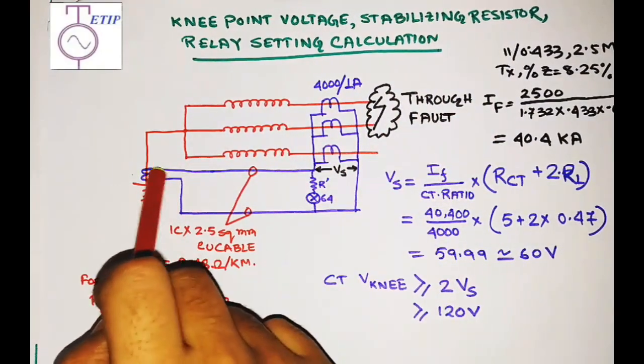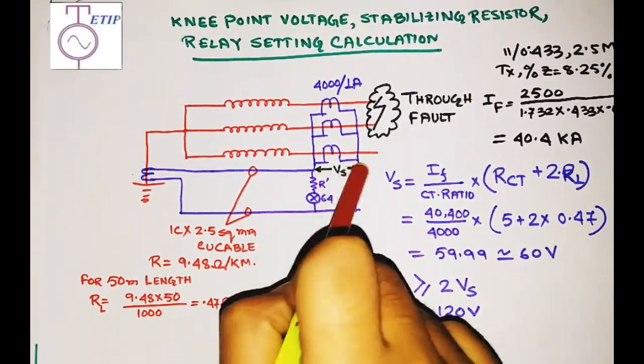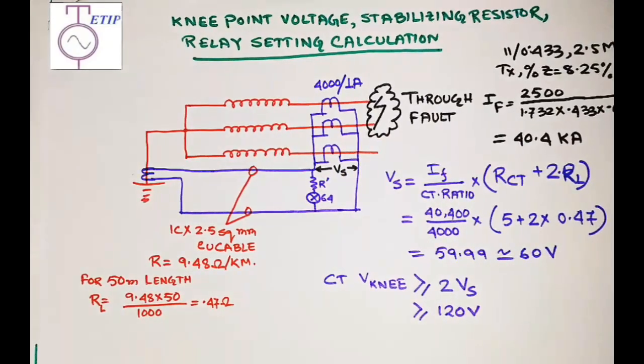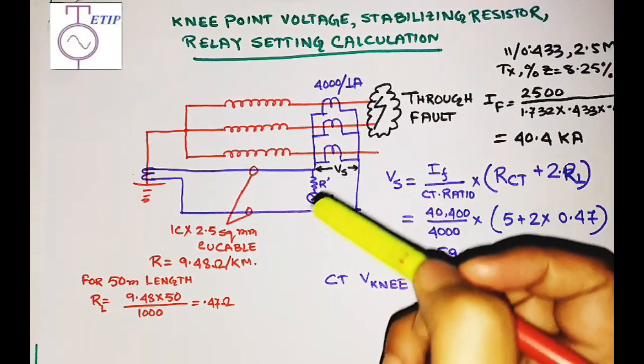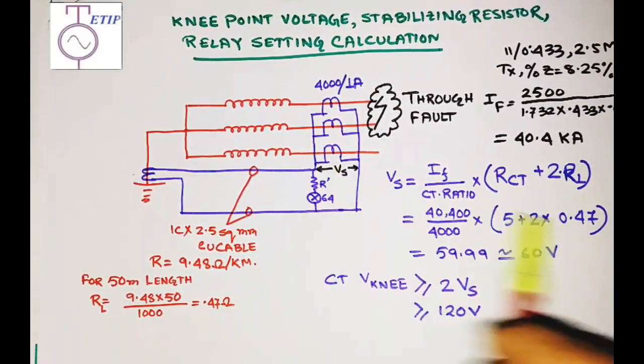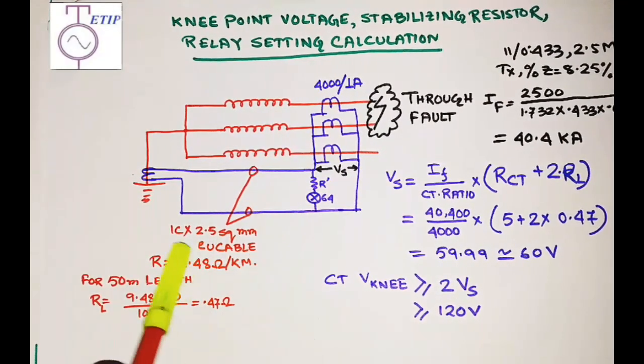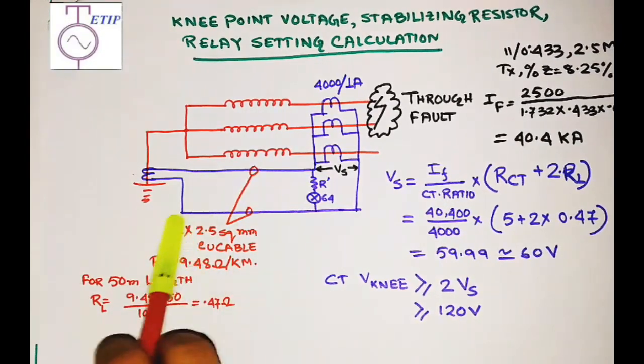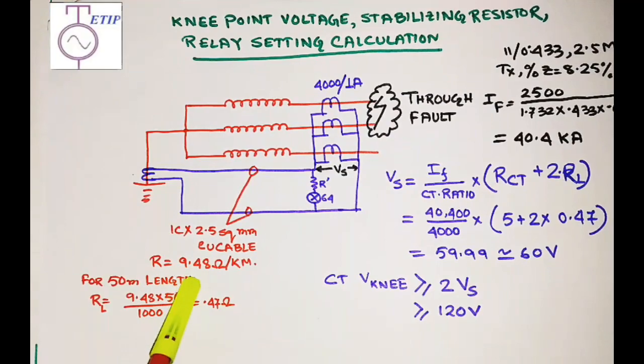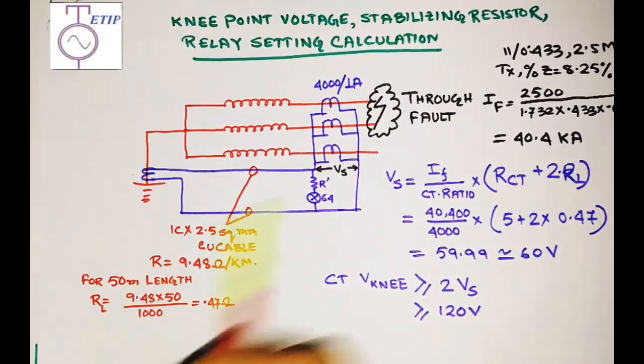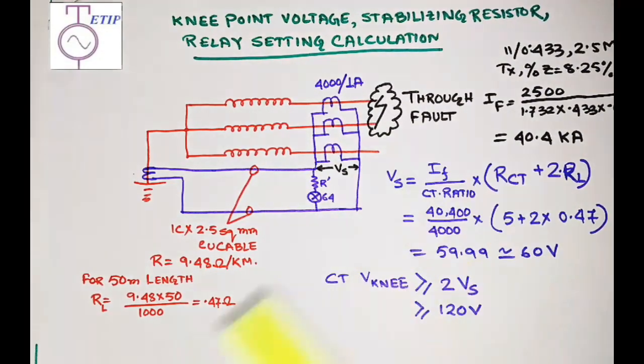There is a possibility that the CTs are placed away from the relay. The conductors connecting them are copper wire and have some resistance — this is the lead resistance Rl. In industry, single-core 2.5 sq. mm copper cables are used, which have a resistance of around 9.48 to 9.5 ohm per kilometer. Suppose the relay is 50 meters away from the CT; then Rl = 9.48 × 50 / 1000 = 0.47 ohm for 50 meters.